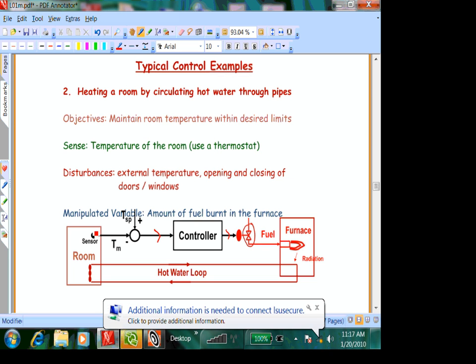The speed at which the water is flowing and the surface area of the heater. So a design change—for example, if you want to go down to minus 10 degrees in Baton Rouge, you need to put in more heat and it's not able to deliver. You can try increasing the fuel, you can burn all the fuel you want, but if it's not able to transfer it to this place, it's not functioning. That would be an example of a design limitation in your heater in the room.